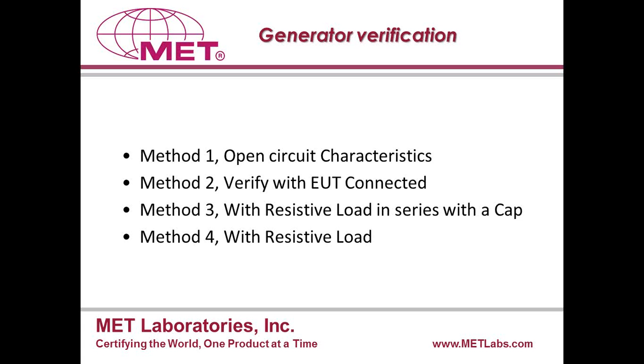First method sounds very simple. It refers to the test generator as a power amplifier. It's assuming the generator is basically a very wideband power amplifier, which would cover the frequency range from DC all the way up to hundreds of kilohertz, if not megahertz, because we want to achieve very fast rise time and fall time. So it says determine the rise time, determine the fall time with the open circuit, determine the slew rate, and so on and so forth. All those things are extremely complicated and extremely time-consuming ways to validate the test method. And you still do not get a clear picture of how the generator would behave when it's hooked up to the actual load. So a large number of labs in the industry would not use that method. It's practically very, very difficult to use that method.